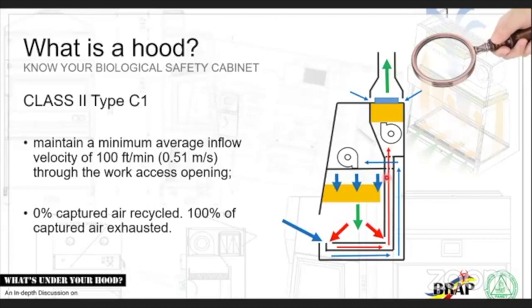So negative pressure spaces are very good to ensure that there is containment. You do not want positive pressure areas in your biosafety cabinet, because if you have positive pressure, imagine blowing into your Zesto juice again. If there are holes, where does the content go? Outside. So we don't want any positive pressure within this area or surrounding this area. We would want everything as negatively pressured as possible. So here, because it's being sucked, it's negative pressure. Here, it's being sucked, it's negative pressure as well. Okay. Now, this is the interesting part. You can hard duct it, or you can thimble duct it or canopy duct it. So that's why they say it's very versatile. You could use it for either one.